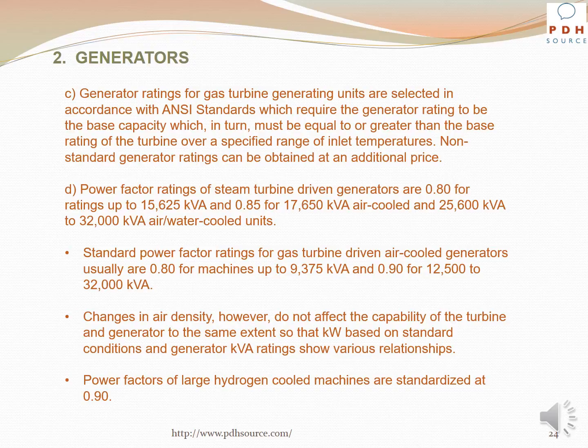Generator ratings for gas turbine generating units are selected in accordance with ANSI standards, which require the generator rating to be the base capacity, which in turn must be equal to or greater than the base rating of the turbine over a specified range of inlet temperatures. Non-standard generator ratings can be obtained at an additional price.